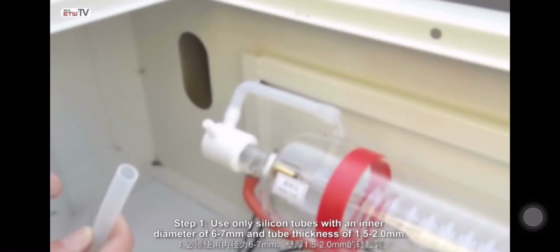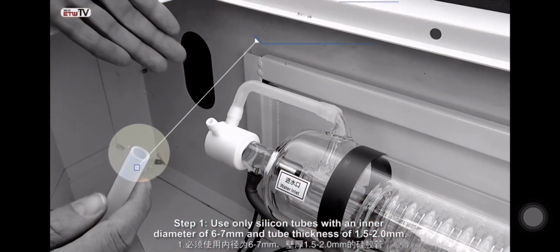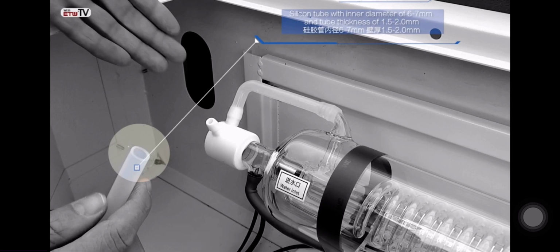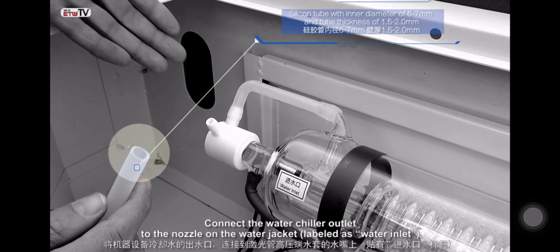Step 1. Use only silicon tubes with an inner diameter of 6 to 7 millimeters and tube thickness of 1.5 to 2 millimeters. Connect the water chiller outlet to the nozzle on the water jacket labeled as water inlet.